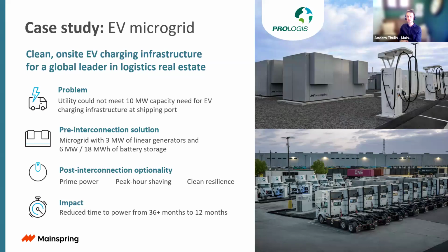What this enables them to do is get power a lot quicker—prime power now, and when the utility eventually arrives, you can either peak hour shave, use it as a backup asset, or introduce an alternative fuel such as hydrogen to further clean up and support Los Angeles' objectives of deploying hydrogen. From a speed perspective, rather than waiting 3+ years for the utility to arrive, the project was able to be up and running in 12 months.